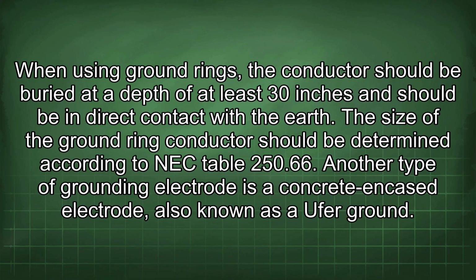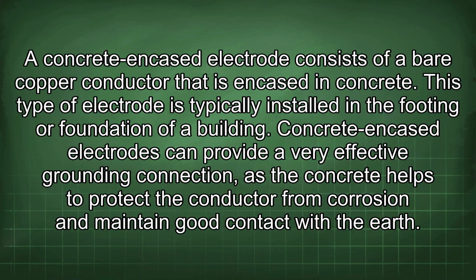Another type of grounding electrode is a concrete encased electrode, also known as a Ufer ground. A concrete encased electrode consists of a bare copper conductor that is encased in concrete. This type of electrode is typically installed in the footing or foundation of a building. Concrete encased electrodes can provide a very effective grounding connection, as the concrete helps to protect the conductor from corrosion and maintain good contact with the earth.